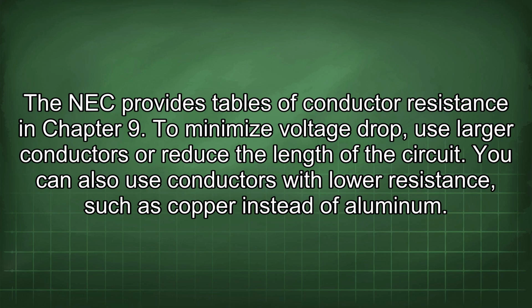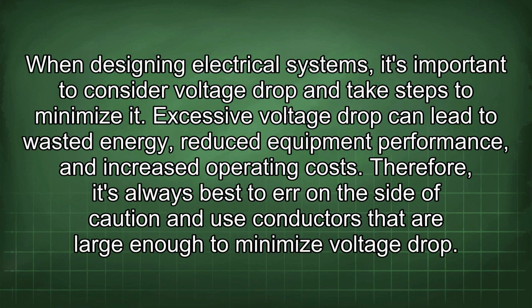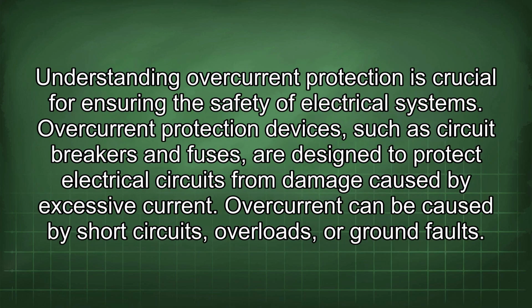To minimize voltage drop, use larger conductors or reduce the length of the circuit. You can also use conductors with lower resistance, such as copper instead of aluminum. When designing electrical systems, it's important to consider voltage drop and take steps to minimize it. Excessive voltage drop can lead to wasted energy, reduced equipment performance, and increased operating costs. Therefore, it's always best to err on the side of caution and use conductors that are large enough to minimize voltage drop. Understanding overcurrent protection is crucial for ensuring the safety of electrical systems.